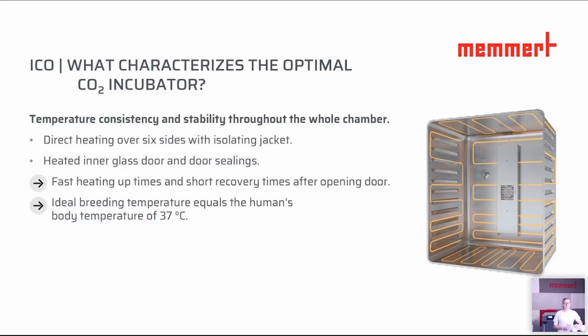On the picture on the right-hand side, you can see our heating system, which obviously provides more heating power in the bottom than in the top, which is done for a quite simple reason. Warm air only goes up. With that special and unique heating system, we can provide fast heating and short recovery times after having opened the door. For most of our customers, the ideal breeding temperature is body temperature, which is 37 degrees Celsius, which our ICO has been perfected for.